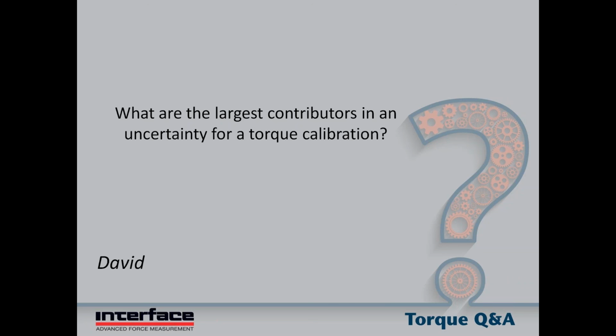Also, when the torque is applied to the moment arm, you have torsional windup of the torque sensor when the load is applied. This allows the moment arm to rotate, and if the load is applied while the moment arm is at some angle other than perpendicular and level, you introduce some errors into the torque measurement that are typically accounted for by using a gearbox and a leveling mechanism and a bubble level to bring the moment arm back to level after applying the load.